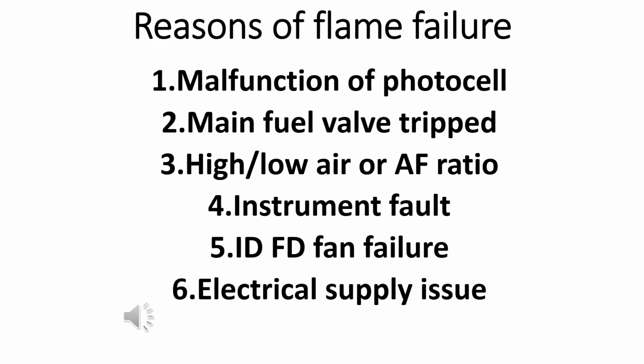Number two is the main fuel valve trip. If your main fuel valve is tripped due to any reason, if your main fuel valve is an auto valve, or if your main is XSV, then there will be an issue of instrument air. If your main fuel valve is operating on instrument air and the failure of instrument air causes the main fuel valve to close, then ultimately our flame will fail.